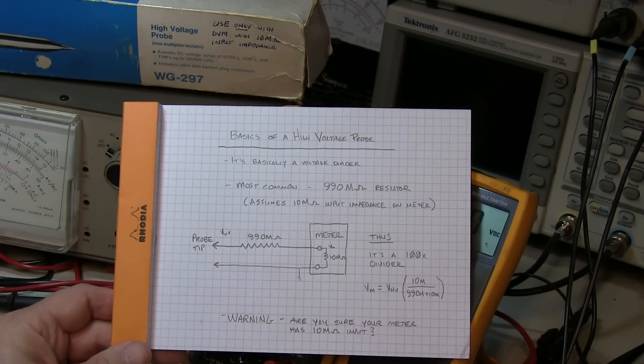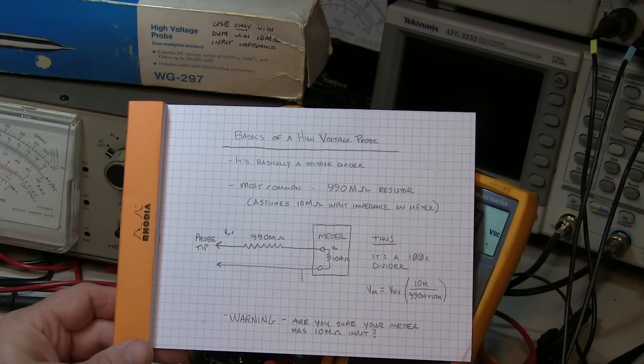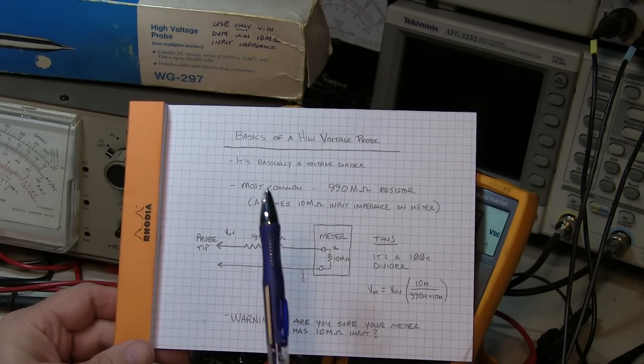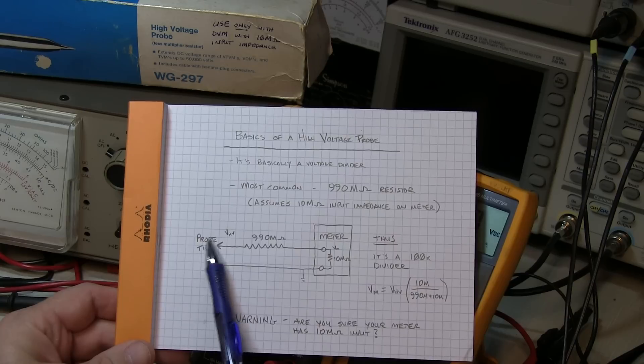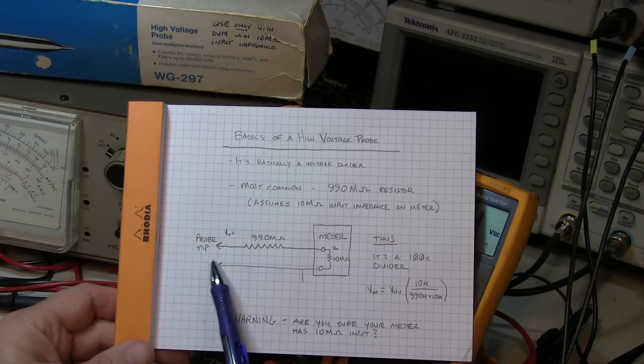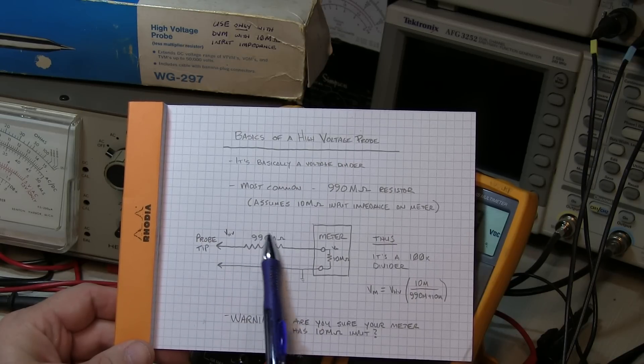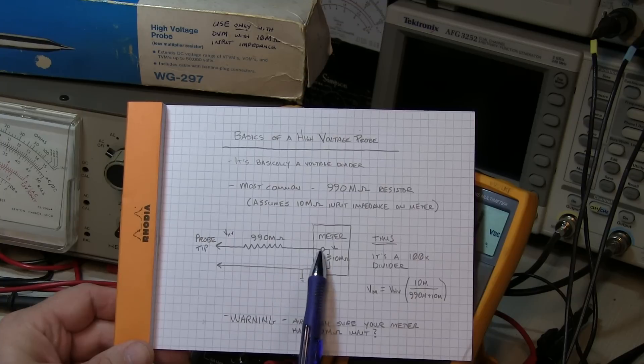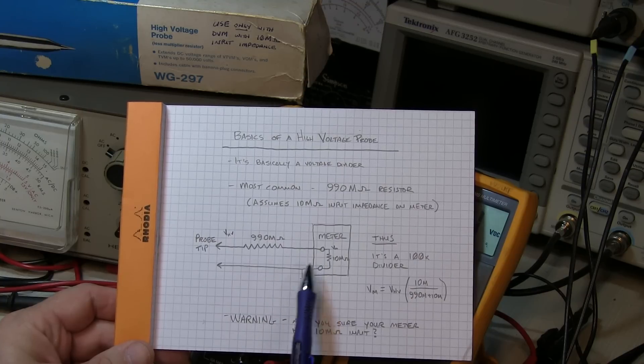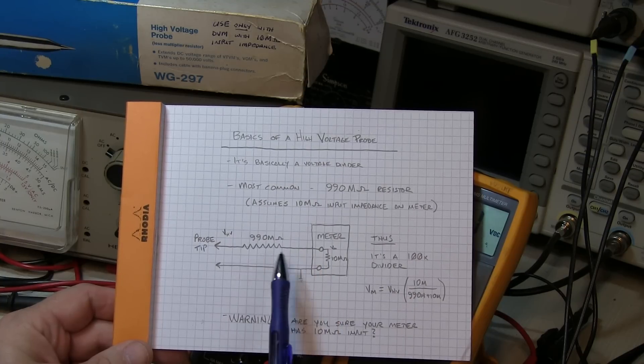A high voltage probe is really nothing more than a voltage divider, where you've got the probe tip here connecting up to your high voltage and then ground, and it has a series resistor that is used in conjunction with the impedance of the meter to create a voltage divider.